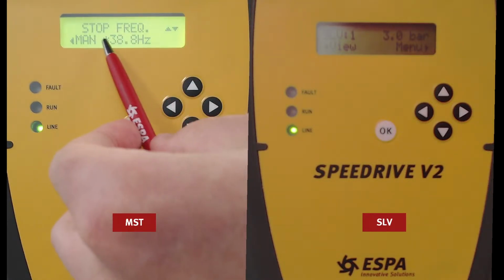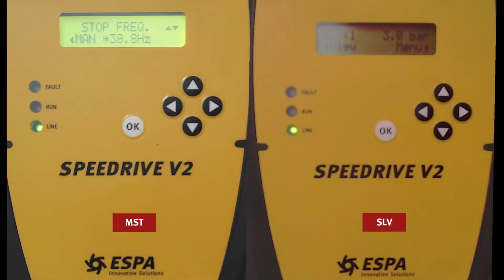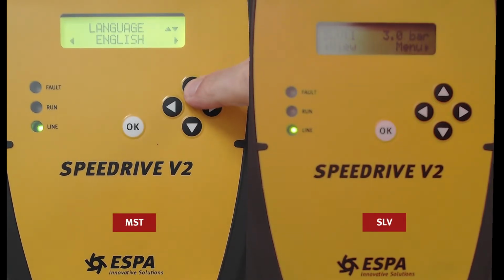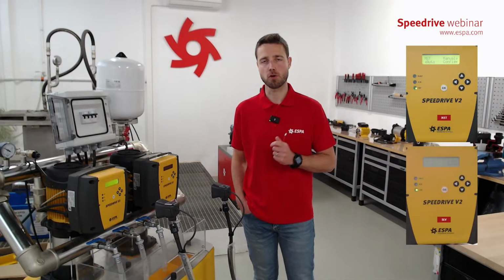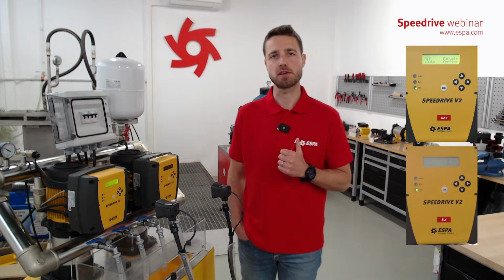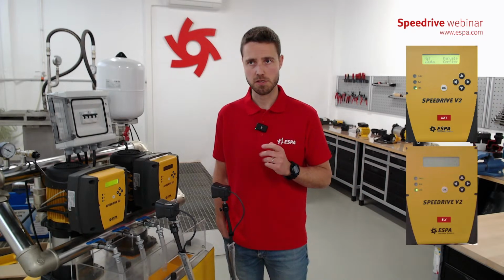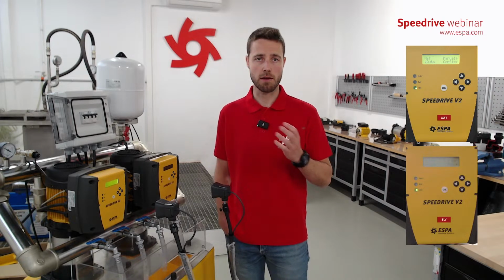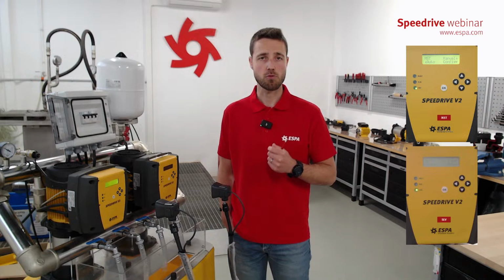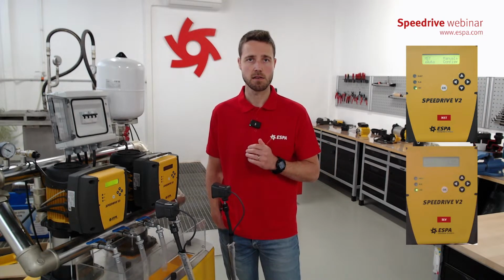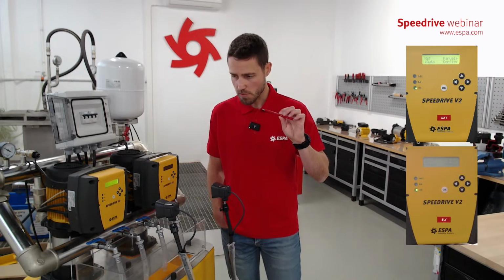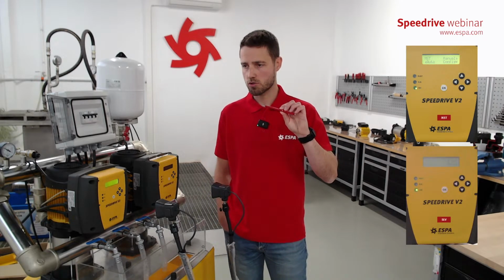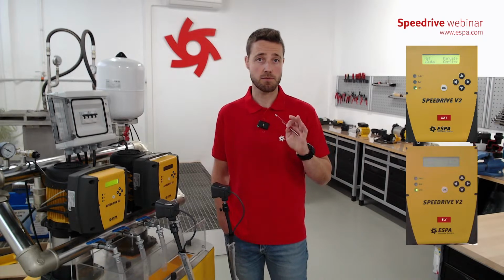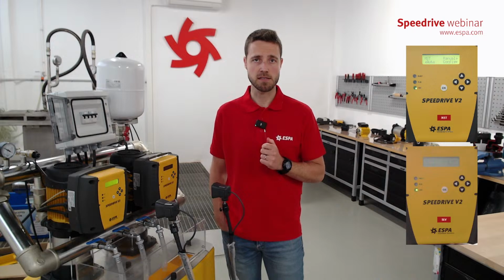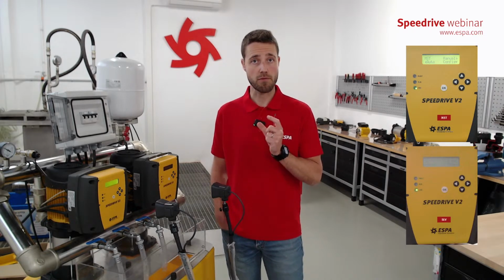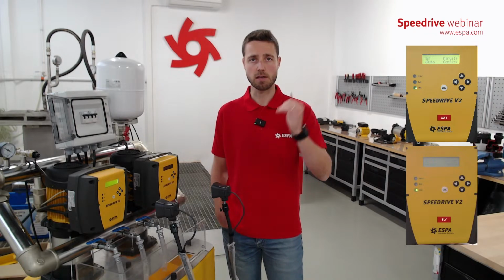Now we have this symbol that indicates that we have to do it manually. So this is one of the most important things that we can check during a startup, that the pump actually stops. And the other common error is the dry running effect that we have already covered in the advanced settings. We have to check that the stop parameter is set at normally 50% of the intensity, and if the pump will not stop when we have no pressure, that it's running high, we have to increase this value.